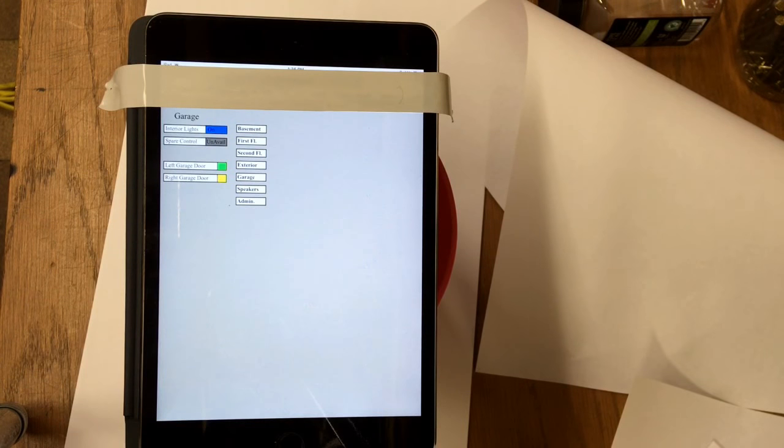Oh, there you go. So it went to light green initially. That's a timing issue with when the input pin gets monitored, translated, and sent to the web page, and that moment when it's between not fully closed and closed, you get that. But it's dark green, so I'm happy. Good to go. The light in the garage is still on. It will remain on until the timer on the garage door opener turns off the light.